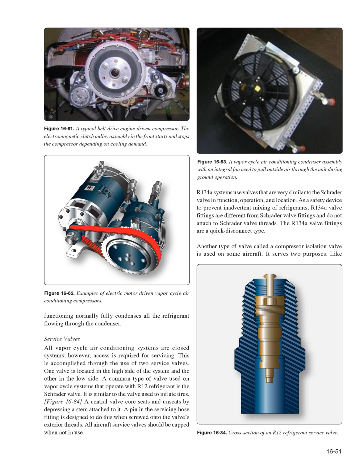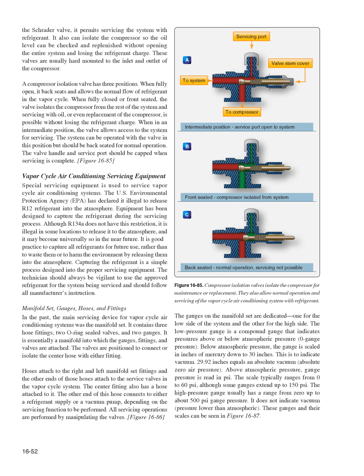Another type of valve is called a compressor isolation valve. Like the Schrader valve, it permits servicing the system with refrigerant. It also can isolate the compressor so the oil level can be checked and replenished without opening the entire system and losing the refrigerant charge. These valves are usually hard mounted to the inlet and outlet of the compressor.